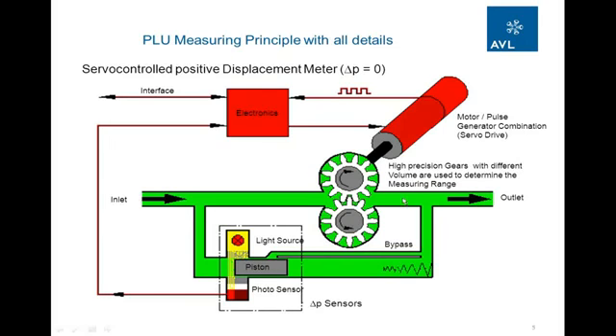If you have an engine and the engine is running with 1 liter per hour, then the 1 liter per hour is coming over these gears, and the piston is standing in this position and makes only very small regulation movements. If now the engine suddenly needs 2 liters per hour, then directly the piston goes in this direction, more light comes to the photosensor, and directly the servo motor speeds up these gears and increases the fuel flow, and exactly to 2 liters per hour. Because if these gears are having more than 2 liters per hour, then directly the piston goes back in this direction and the servo motor speeds down.